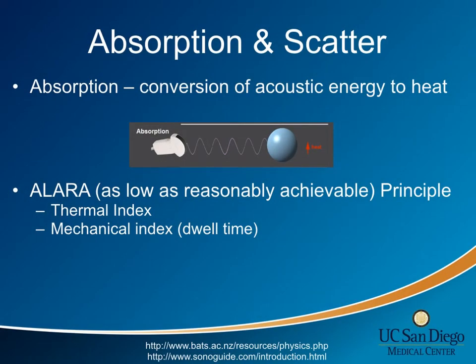Absorption is the conversion of acoustic energy into heat. This is where the ALARA principle comes into effect. That is to say that ultrasound exposure should be as low as reasonably achievable because of the potential for tissue heating when the thermal index exceeds 1. Exposure can be reduced through the use of output control and/or by reducing the amount of time the beam is focused in one place.